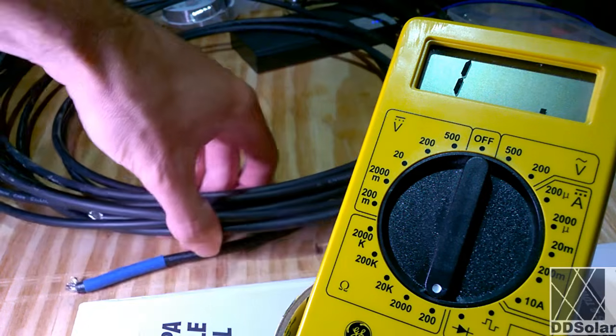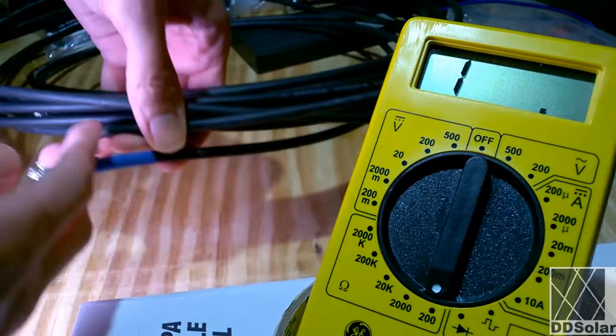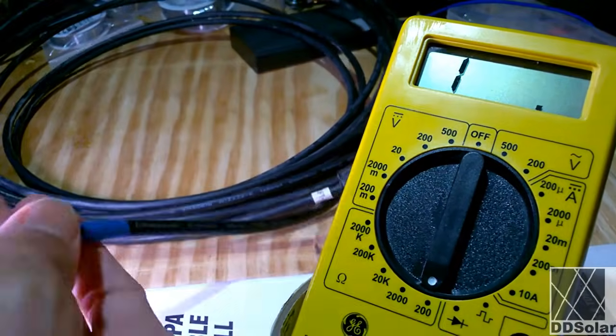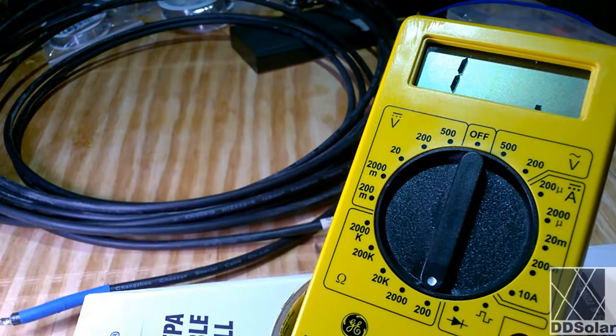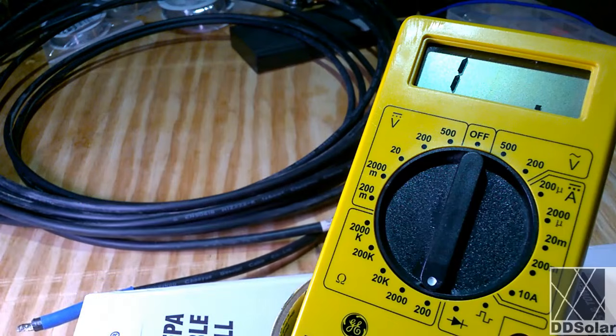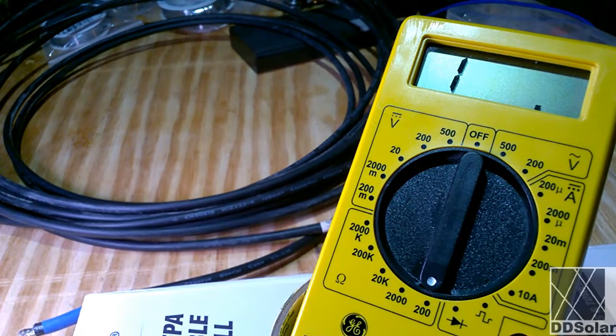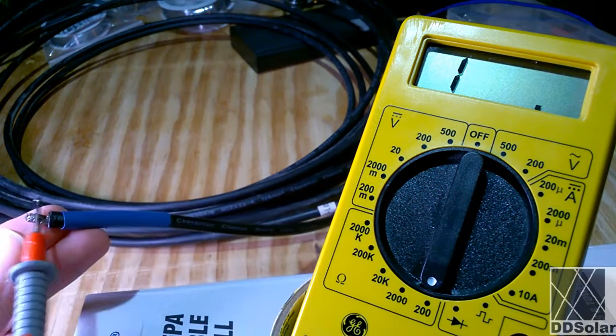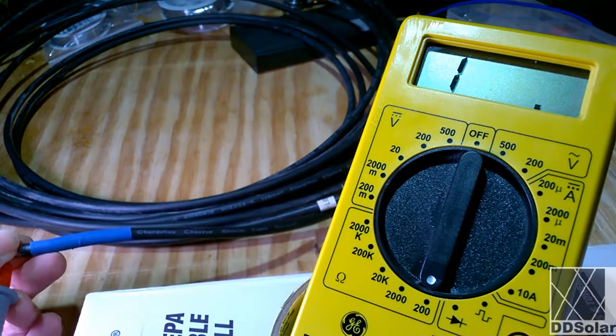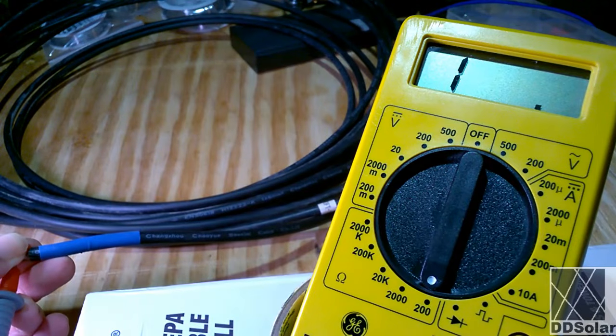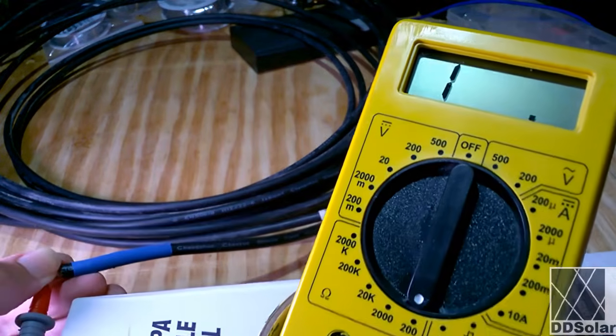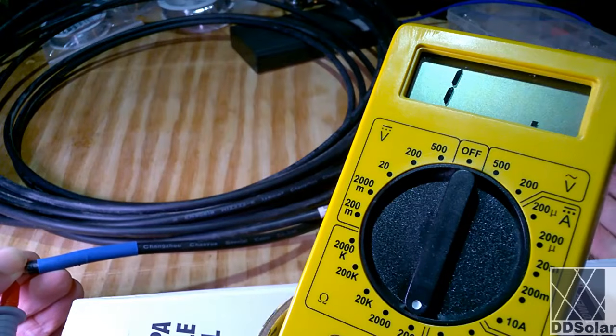So here's some old solar panel cable I have. You can see the end has been cut off. This is a used cable. And what I'm going to do is check this cable to see which one is which. I don't know. It's a pile of cables, and this could be running underground, or it could be in a large installed system or anywhere. But I'm going to go ahead and touch my probes to one side of a wire that I see exposed, and you want to make sure it's not a live wire. In this case, I know it's not. It's just sitting on my work table here.